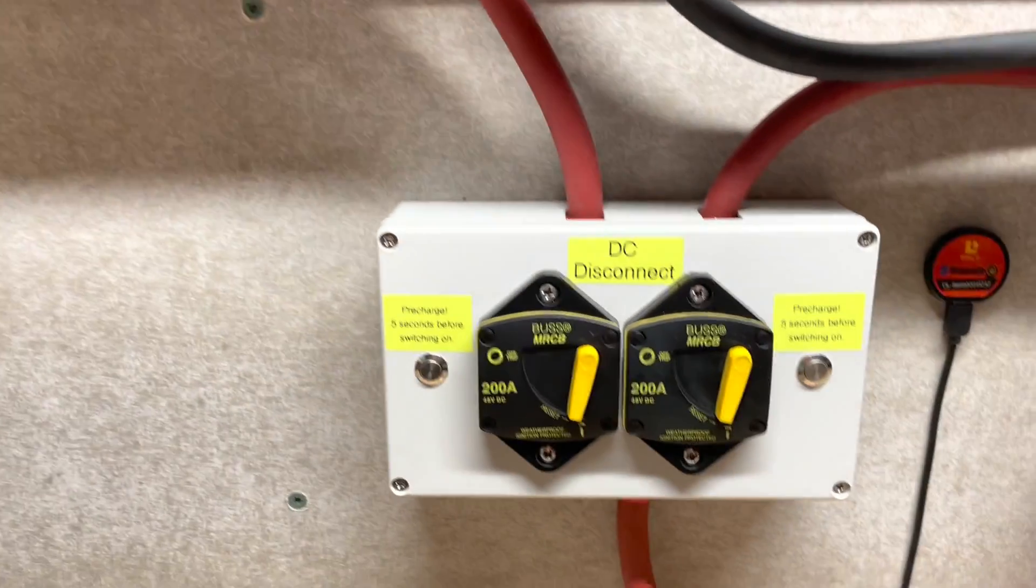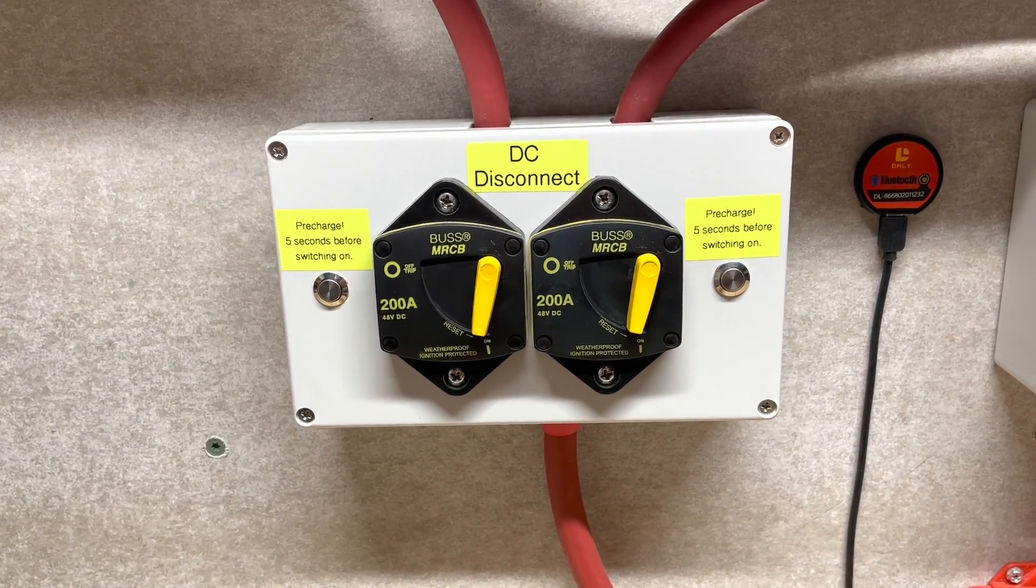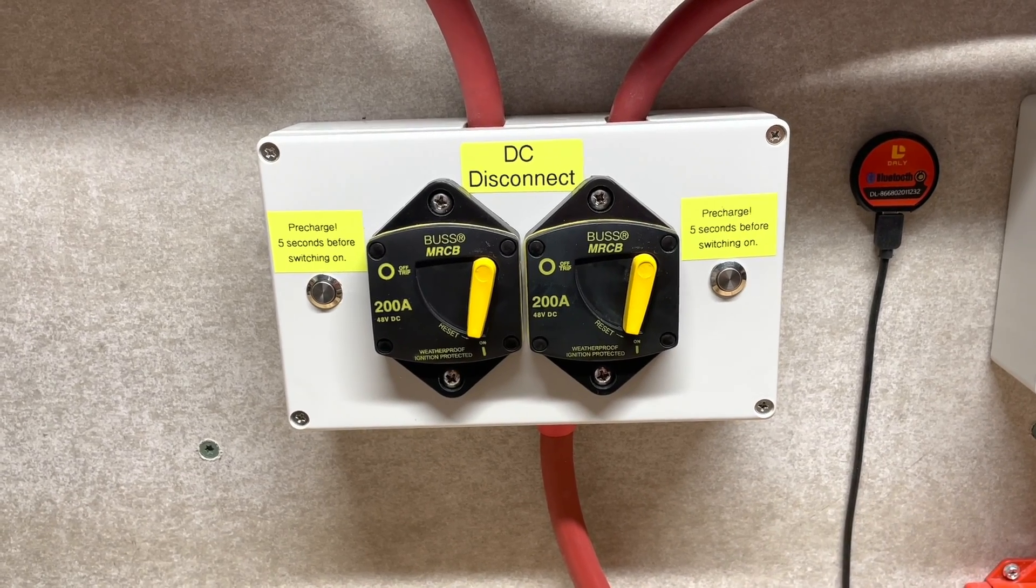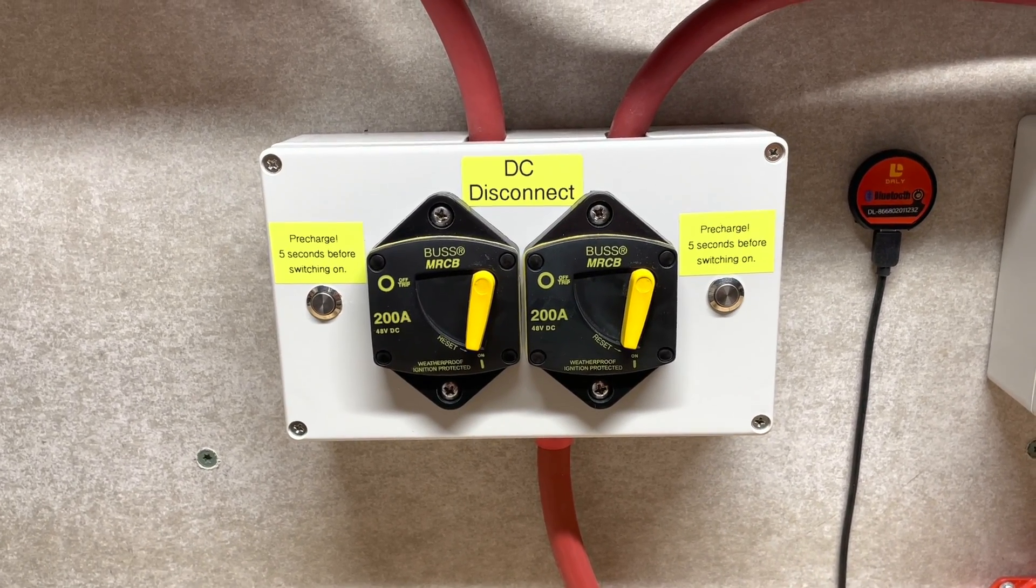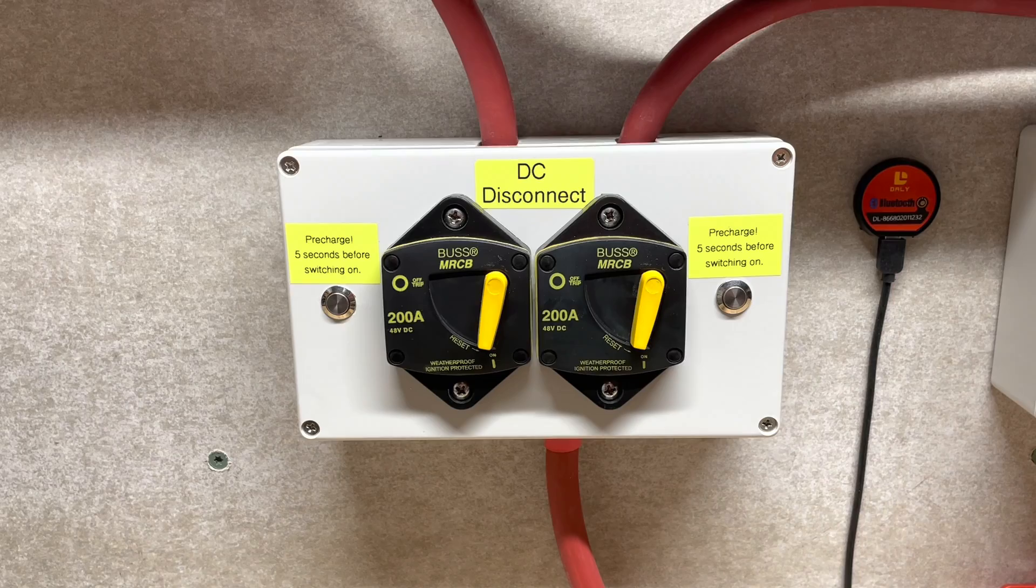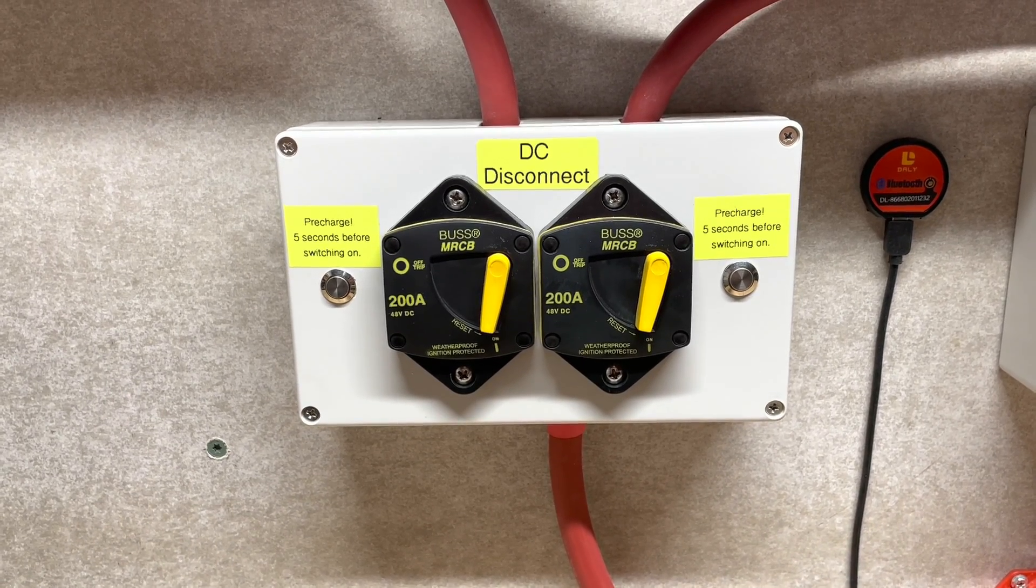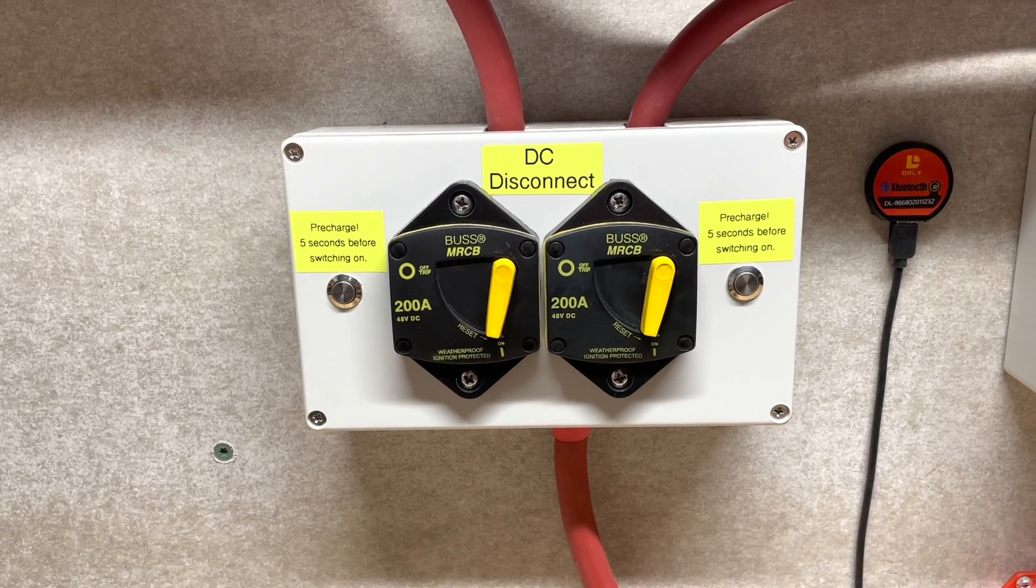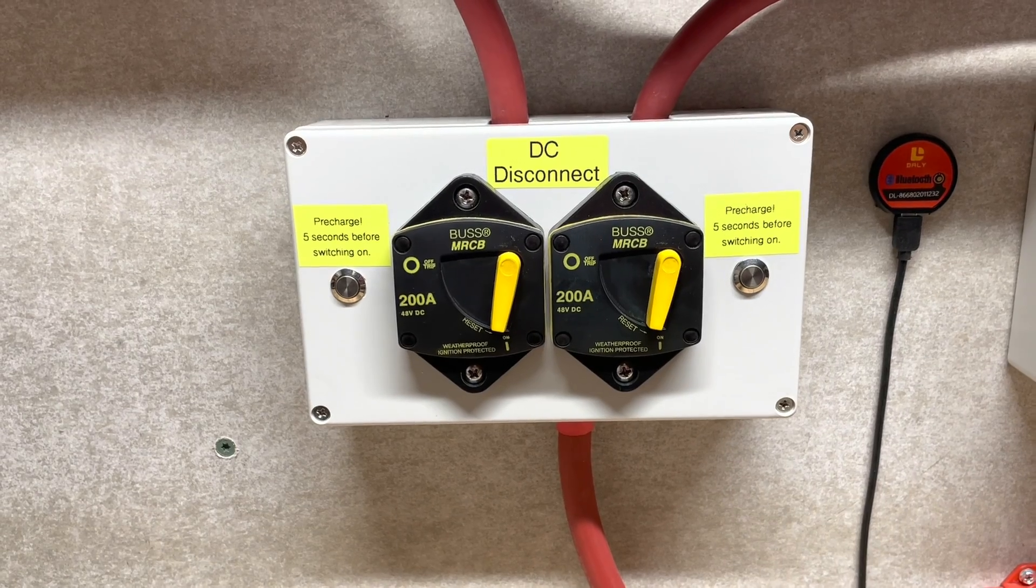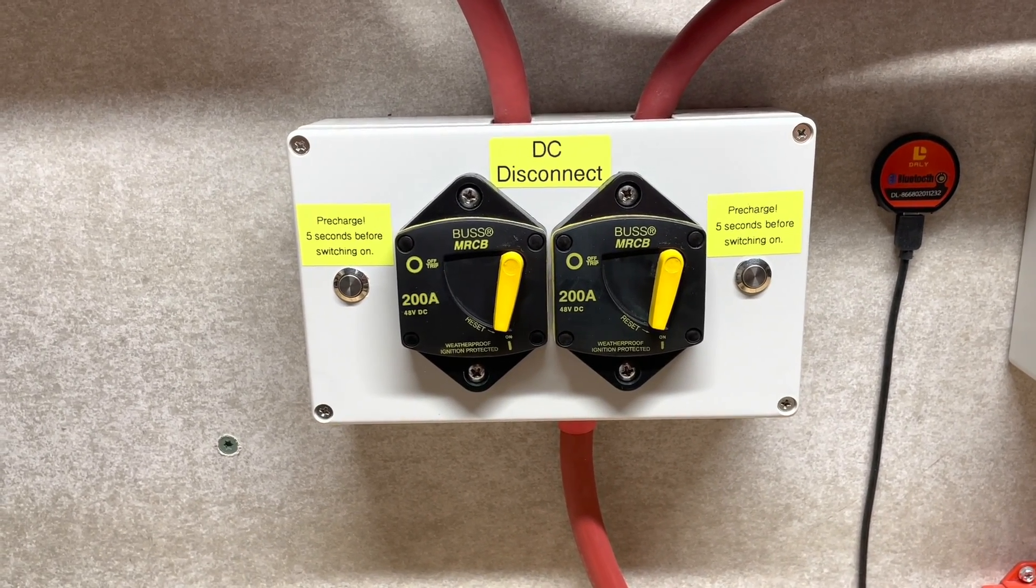DC disconnect - I have resistors wired in there so I can charge the inverters before throwing the switch, which you don't want to be doing. It's hard on your inverters, it's also hard on your BMS to take a surge like that, so charging them slowly.